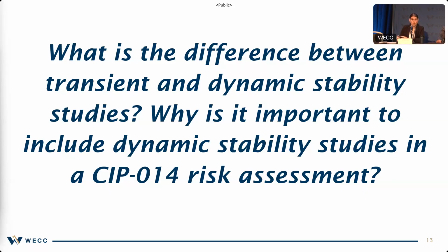So when we talk about dynamic stability, or an instability type assessment, a dynamic stability study is essential to determine whether or not the nearby elements can course correct to accommodate a change — like a loss of load, loss of generation, or a lightning strike — whether those devices can accommodate and course correct, maintaining voltage and frequency within a certain threshold. That's what you're looking at with dynamic stability. It's a wider area assessment, looking at whether the loss of these elements can be accommodated by the remaining system. Thank you, Jamie.